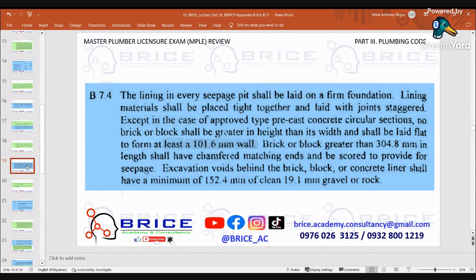The lining in every seepage pit shall be laid on a foundation. Lining material shall be placed tight together and laid with joints staggered. Except in the case of approved type precast concrete circular sections, no brick or block shall be greater in height than its width and shall be laid flat to form at least 101.6 mm wall. Brick or block greater than 304.8 mm in length shall have chamfered matching and be scored to provide for seepage. Excavation voids behind a brick, block, or concrete liner shall have a minimum of 152 mm of clean 19.1 mm gravel or rock.